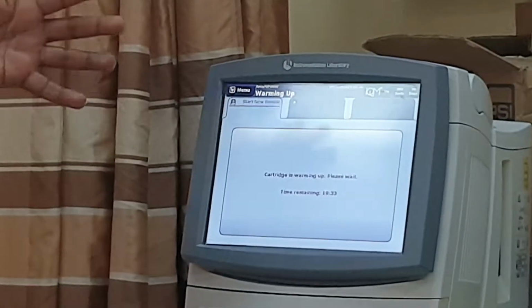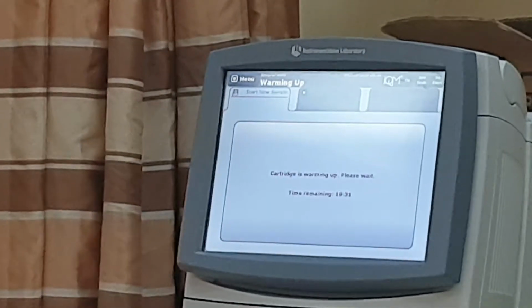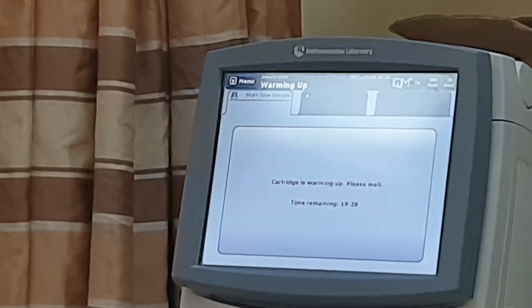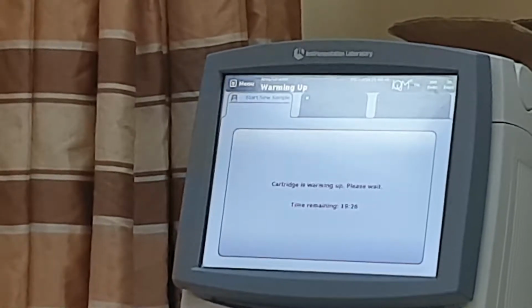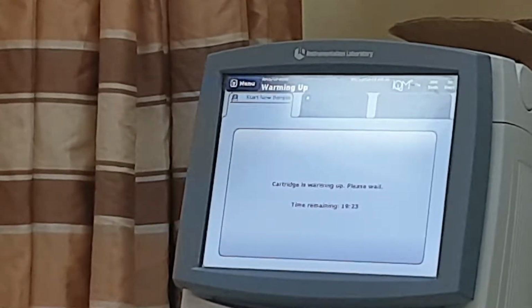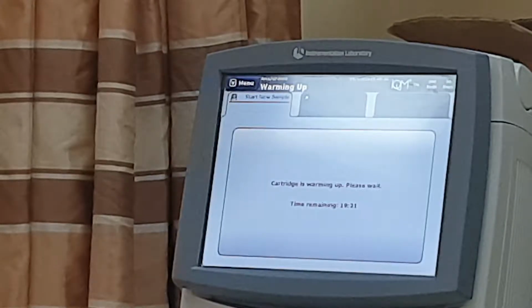The machine is very easy to use. We run ABG, VBG, and capillary samples also at the same time. Firstly, we have to talk about the cartridge. The cartridge includes 300 tests. It will not consume the number of tests if I run the control, because I have so many controls running per day, so we will not consume it as a number of tests. So we have 300 tests per cartridge.